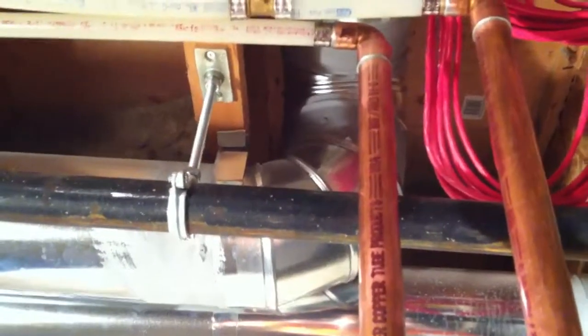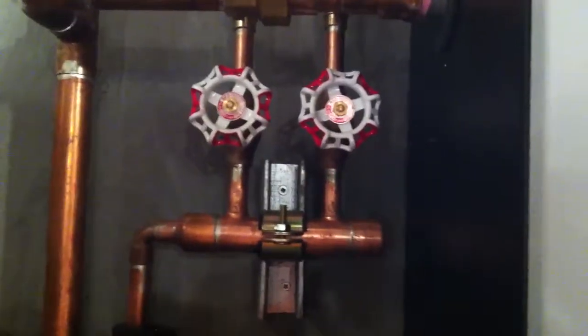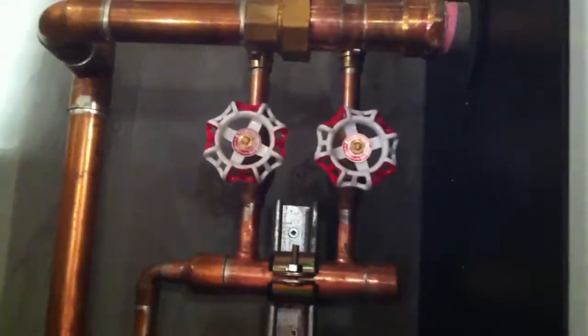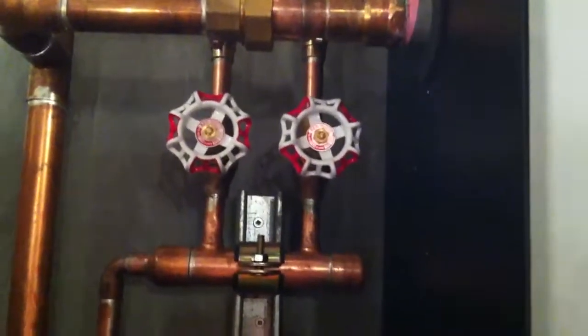The other end of this all is coming back to the hot water tank. This is the outlet on the hot water tank going out to the house. It ties into these two plastic lines — those two are feeding the house. So that's where the hot water starts: comes out of the tank, goes out to the house, and then comes back on these two lines. In a nutshell, that's a domestic hot water recirc system. We'll turn those valves to make sure we've got equal flow in both pipes, because they're not the same length. The valves will compensate for that, and she's all good to go.